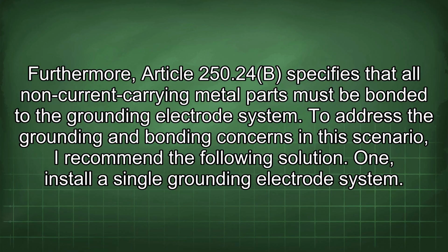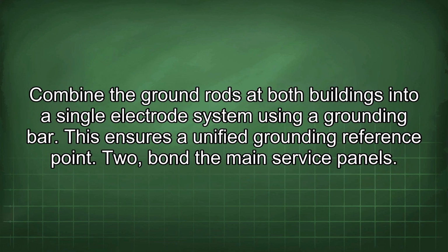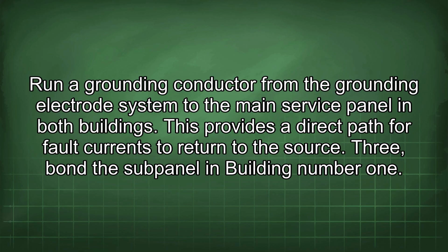To address the grounding and bonding concerns in this scenario, I recommend the following solution. 1. Install a single grounding electrode system. Combine the ground rods of both buildings into a single electrode system using a grounding bar. This ensures a unified grounding reference point. 2. Bond the main service panels. Run a grounding conductor from the grounding electrode system to the main service panel in both buildings. This provides a direct path for fault currents to return to the source.